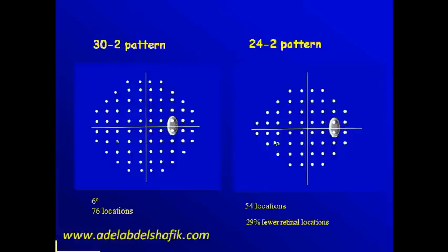Reducing the number of test points from 76 down to 54, this means a shorter test time. The problem with the static field, it takes a long time so the patient starts to lose concentration. So we're trying to get information in a quicker way. One of the things, we stop doing the 30 degrees and we shift to doing the 24. The 24 will get almost the same information and we get it in a shorter time.